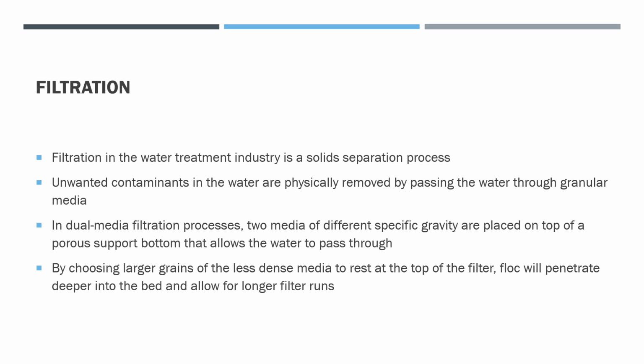placed on top of the other, which all sits on top of a porous plate bottom that allows the water to pass through. And by choosing larger grains of less dense media that rest on top of the filter, the floc will penetrate deeper into the bed and allow for longer filter runs.